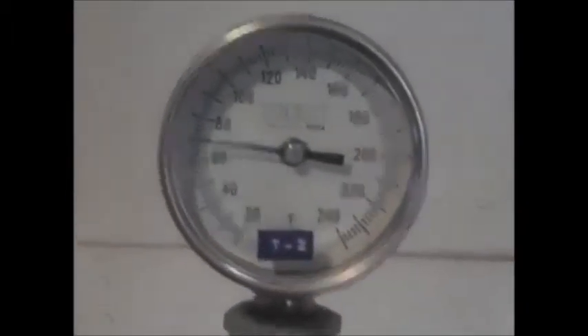Now we're going to demonstrate the air sparge. Right now the valves are open that would go out to the wells. And Todd is closing one of the valves. You can watch the pressure build. Operating right now at about 170, I believe, on the temperature gauge. And cooling to about 70 degrees Fahrenheit. So that's the operation of that. There you see the fan running to cool it.